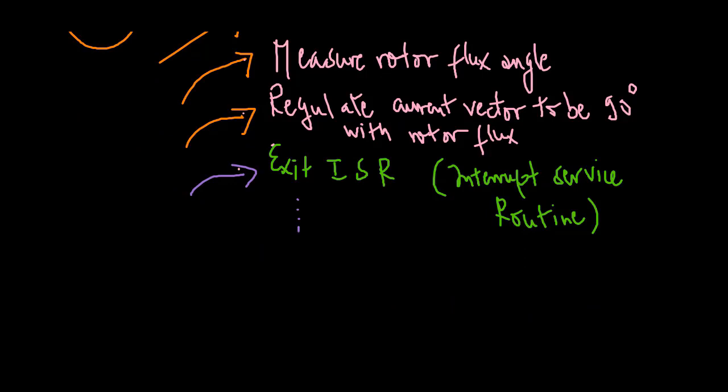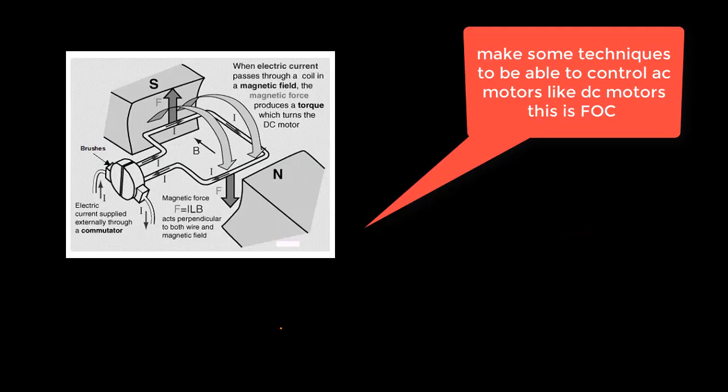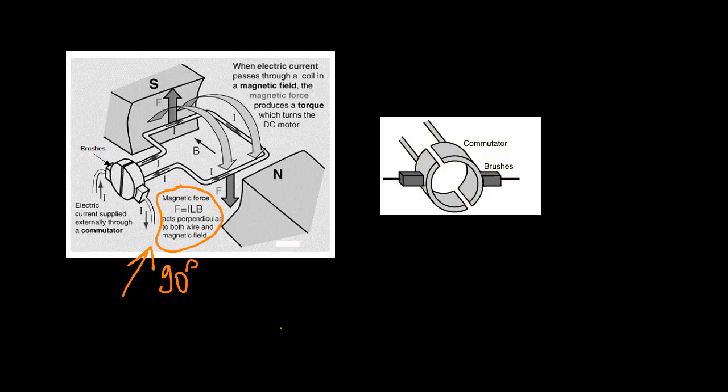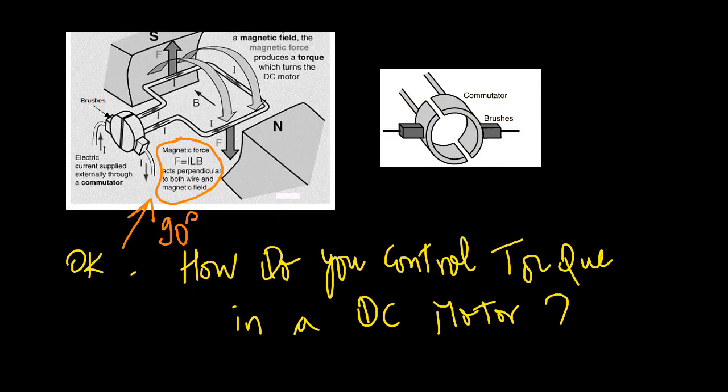Field oriented control, FOC, was developed in the early 1970s and made it feasible to control the induction motor as a separately excited DC motor. All motors do field oriented control in one form or another. Even brush DC motors do FOC — they just accomplish it mechanically by using brushes and a commutator. Controlling the torque on a brush DC motor is fairly easy to understand, so let's start with that.